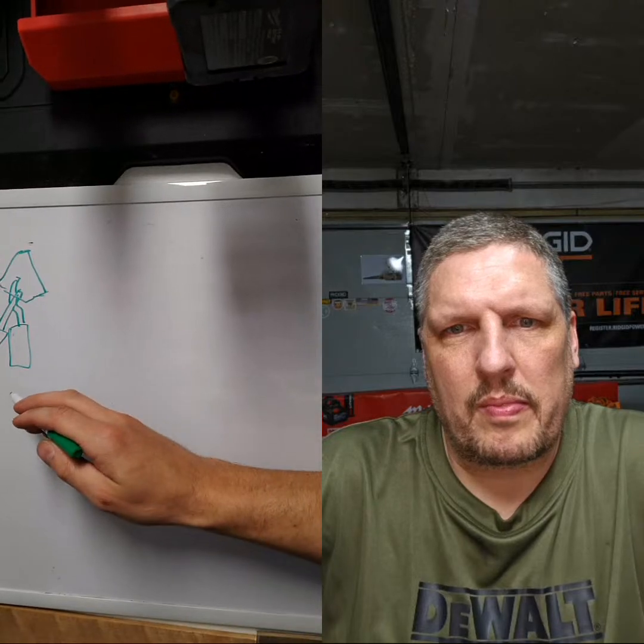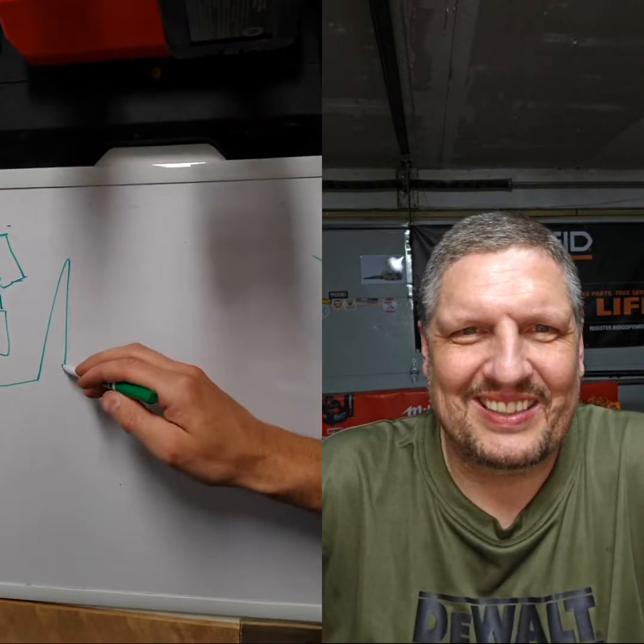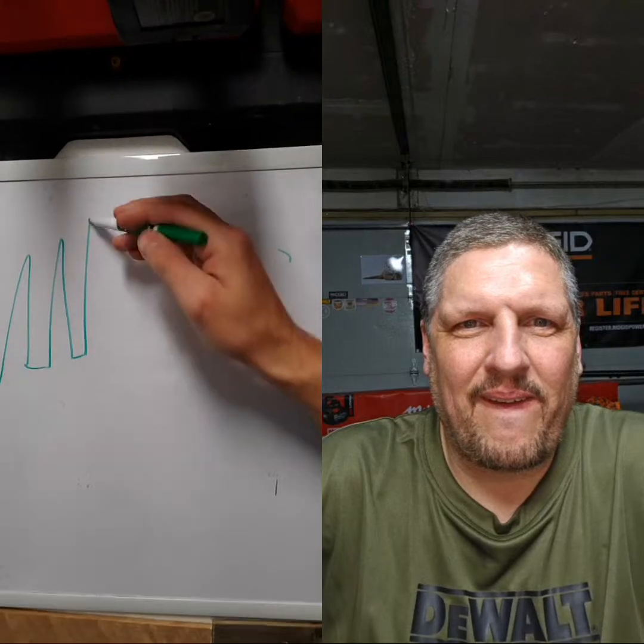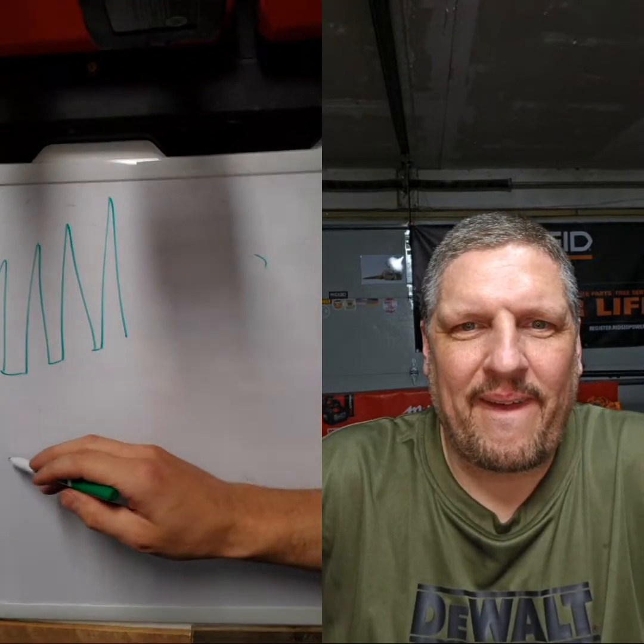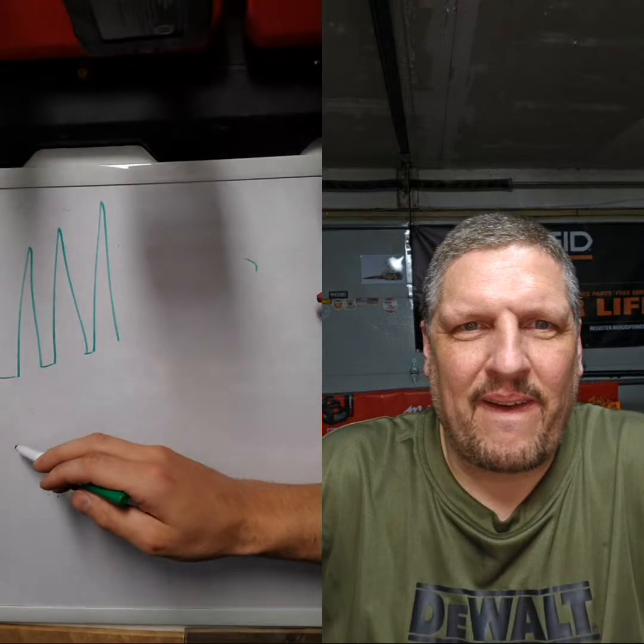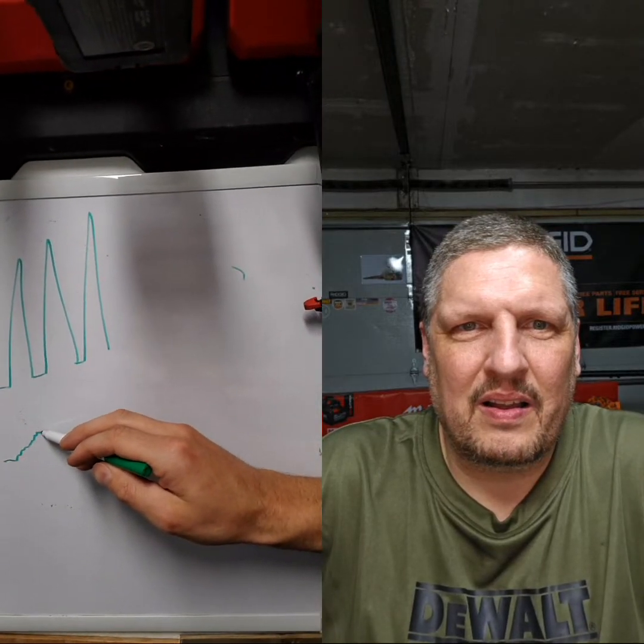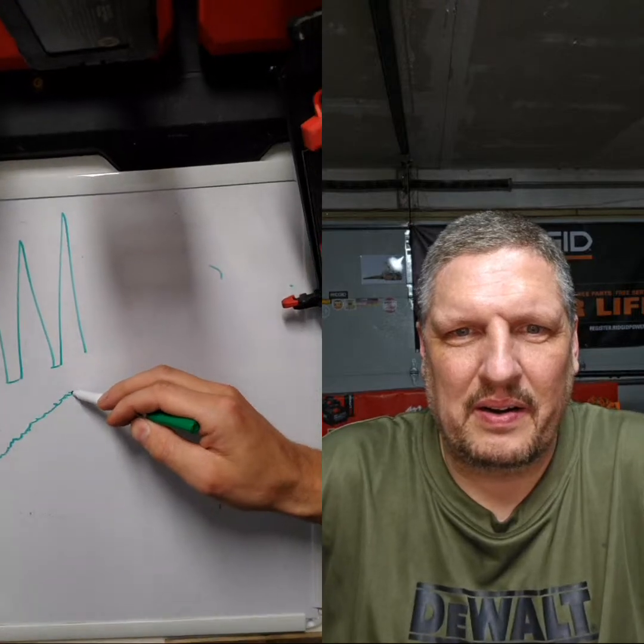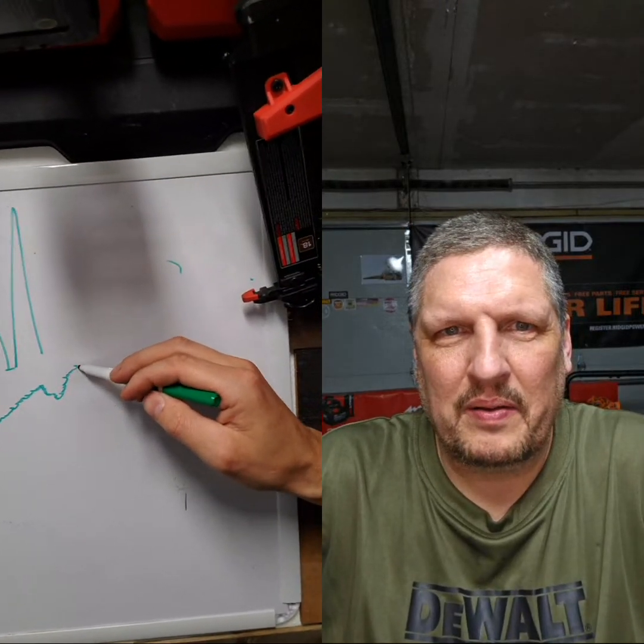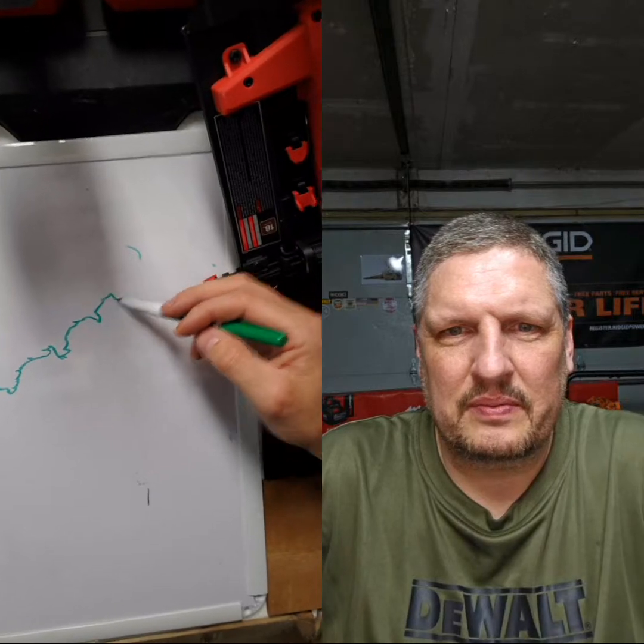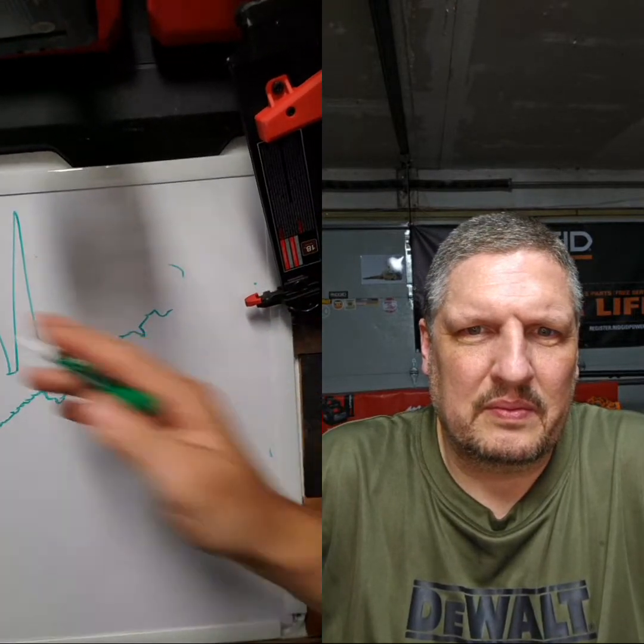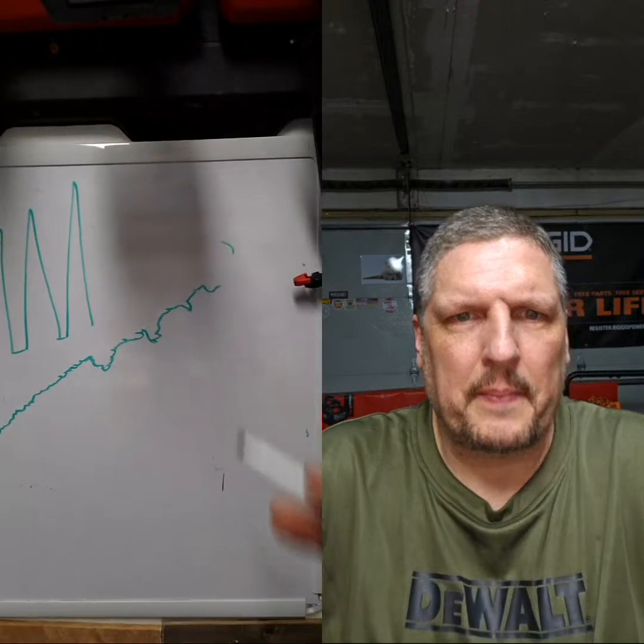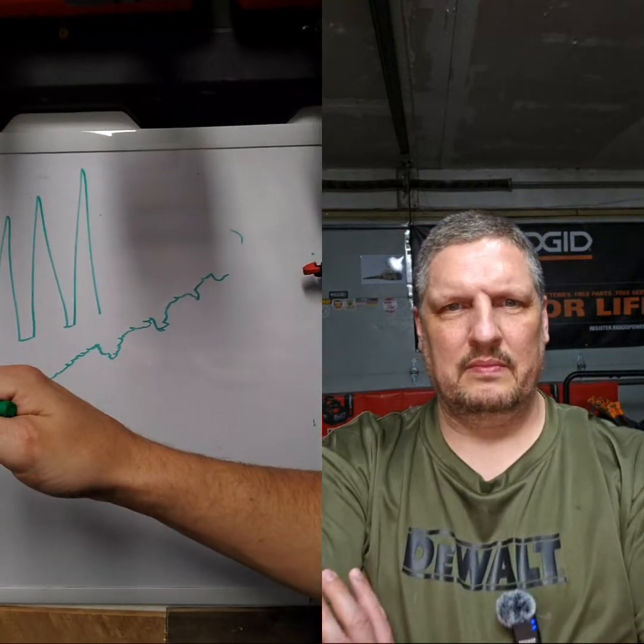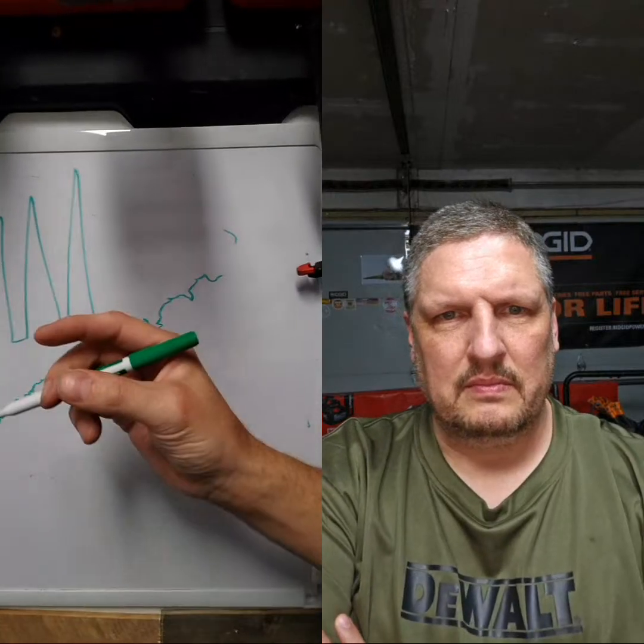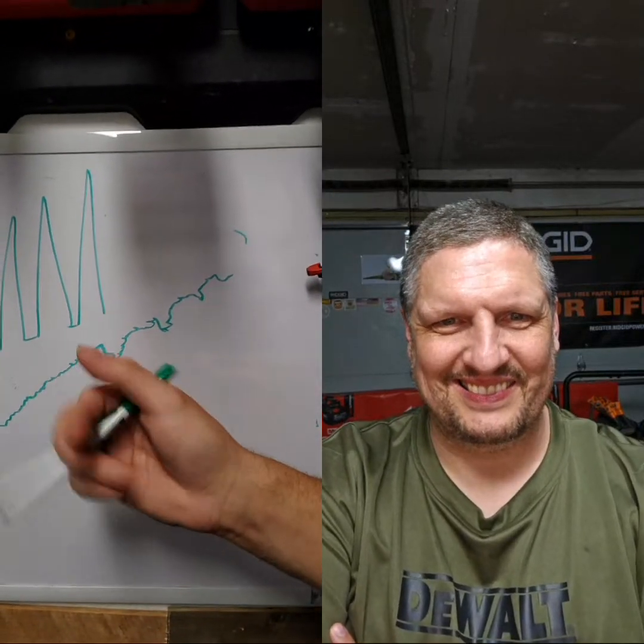If you looked at it with a graph, you wouldn't see it as an arc and an arc and an arc and an arc. What you're going to see that trips an arc fault breaker when you have a problem looks more like this. Several of them, like that. That's what it looks like. And it's that sustained, not pulsing arc, but that sustained drag of a draw, combined with the fluctuation of amperage, because it's sensing the amperage, right? That's what's going to trip an arc fault breaker.